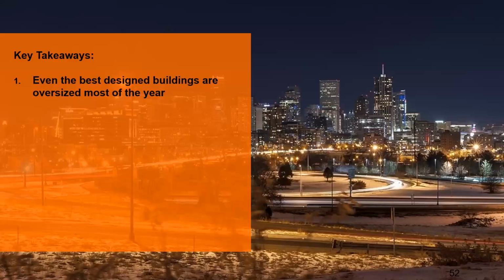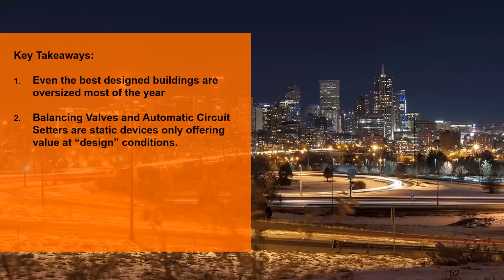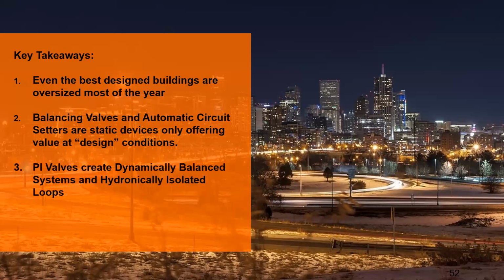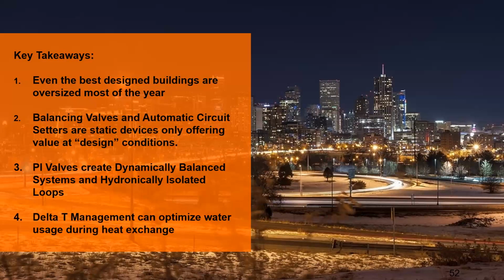So the key takeaways from today are: even the best designed buildings are oversized most of the year. Balance valves and automatic circuit setters are static devices only offering value at design conditions. Pressure independent valves create dynamically balanced systems and hydronically isolated loops. And last but not least, delta T management can optimize water usage during heat exchange.